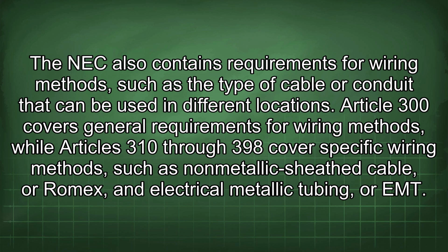The NEC also contains requirements for wiring methods, such as the type of cable or conduit that can be used in different locations. Article 300 covers general requirements for wiring methods, while Articles 310 through 398 cover specific wiring methods, such as non-metallic sheath cable, or ROMEX, and electrical metallic tubing, or EMT.